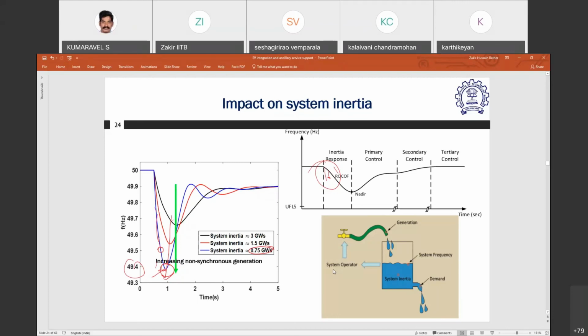We can actually have inertial support from different sources. One we call virtual inertia, or emulated inertia, or synthetic inertia, where these renewable energy sources are provided with supplementary control, which detects the RoCoF in the system and then commands the generator, be it solar or wind, to release power quickly into the system. That is emulated or virtual inertia, and it can to some extent address this lack of diminishing inertia.